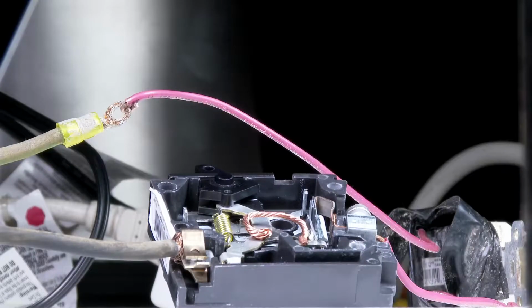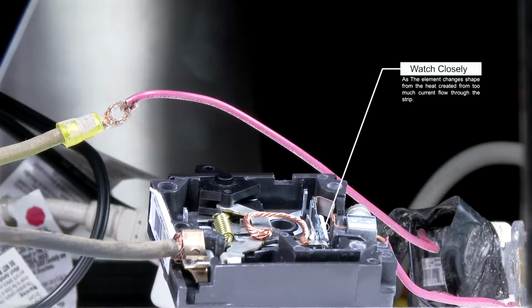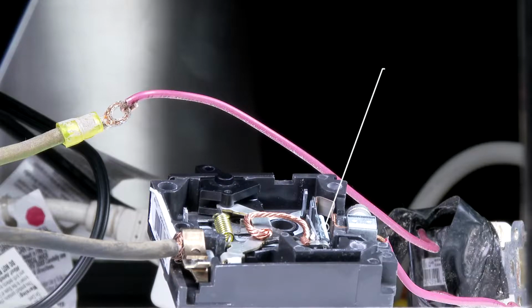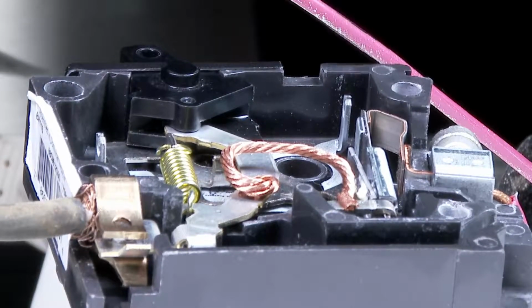We now have too many appliances running on one outlet, which has created a situation where the current draw of the appliances exceeds the amperage rating of the circuit breaker. This overcurrent condition heats up the bimetallic element, changing its shape to the point where it releases the lever, trips the circuit breaker, and interrupts our circuit.